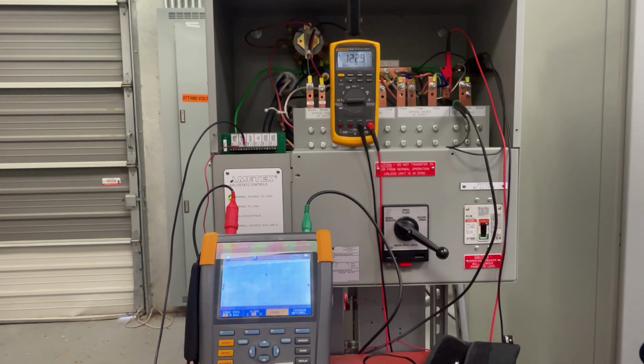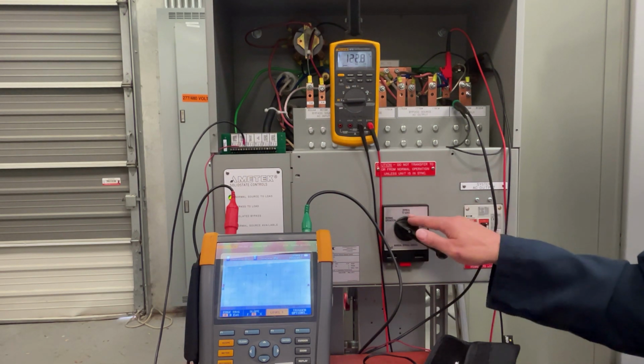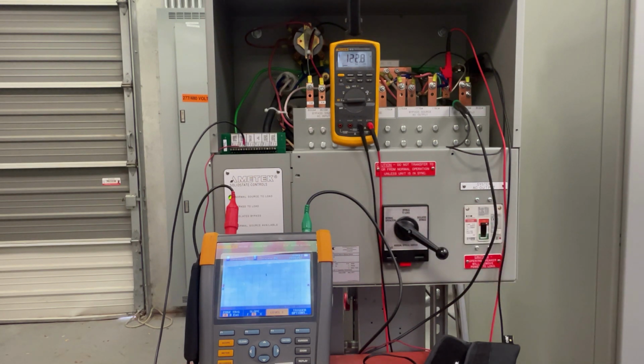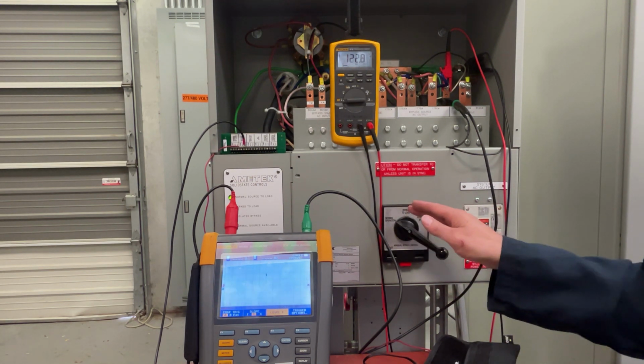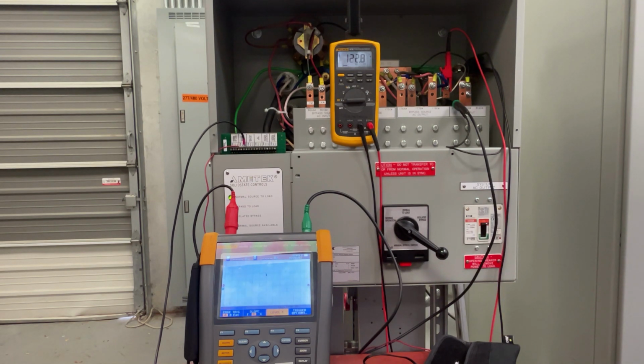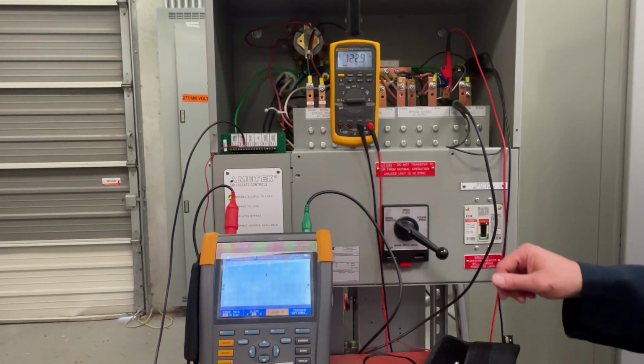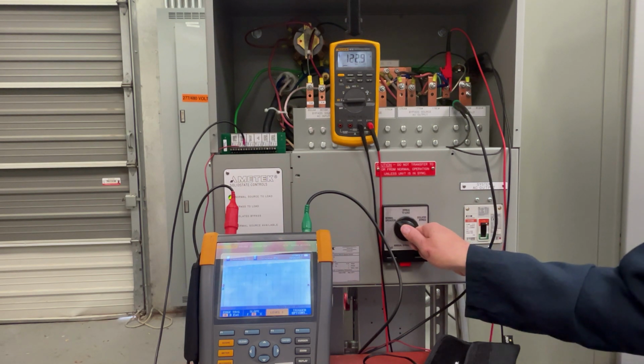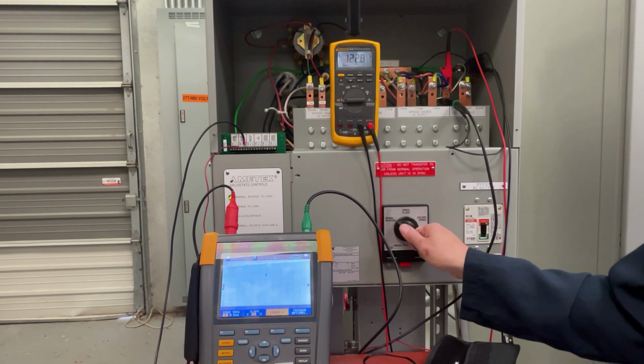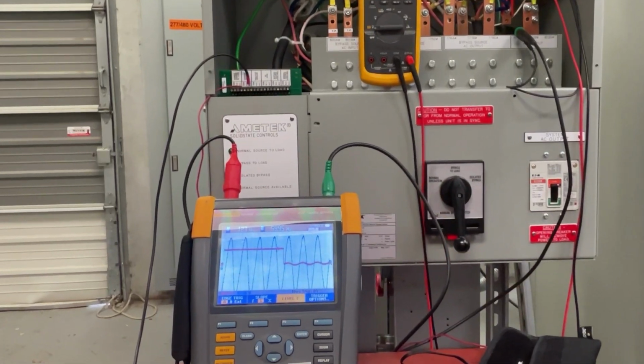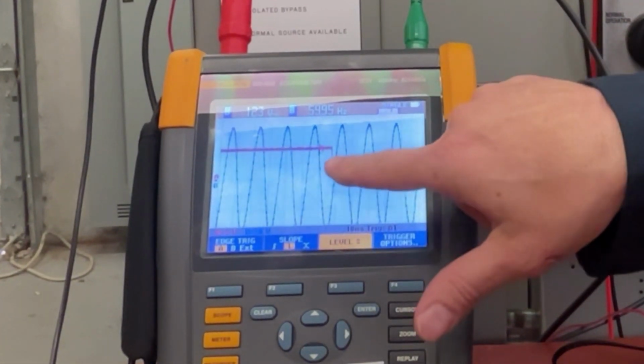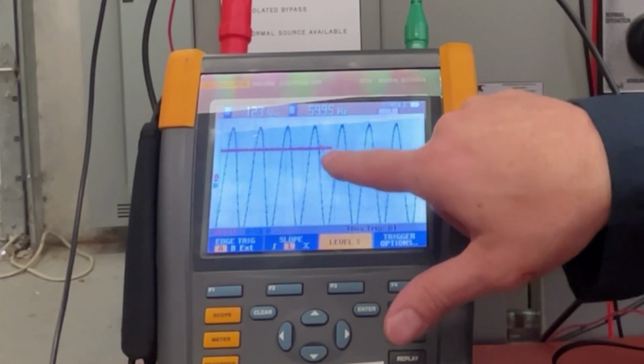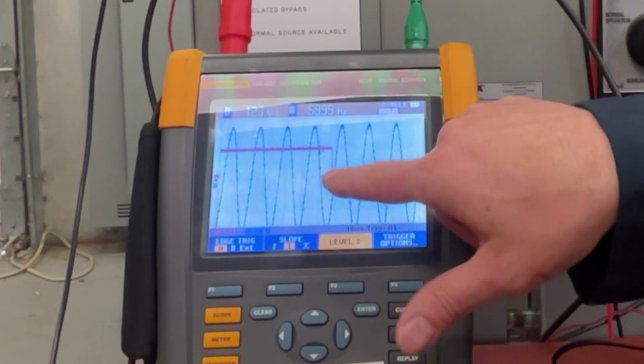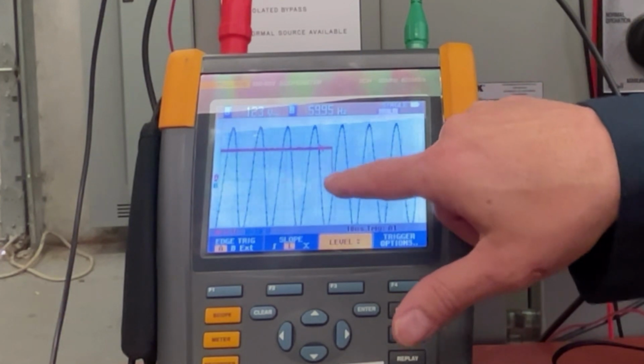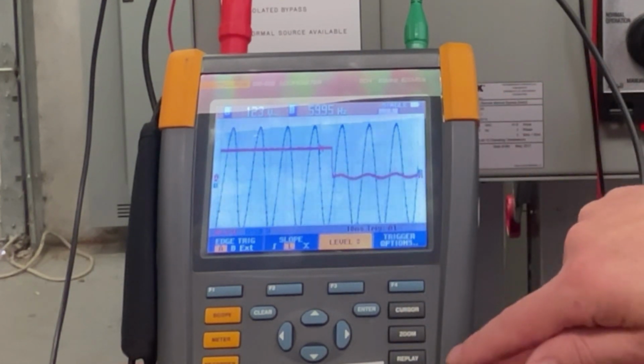and then you can see that there is no break in between when we go from normal operation to bypass operation, and then we will do the same. We'll go from bypass operation to normal operation. Okay, so we've got everything set up on the oscilloscope. So what I'm going to do now is I'm going to go from the normal position to the bypass to load position. And as you can see on the screen there, the red going down, that is when the trigger from the contact disappears. So that's when the actual transfer took place.